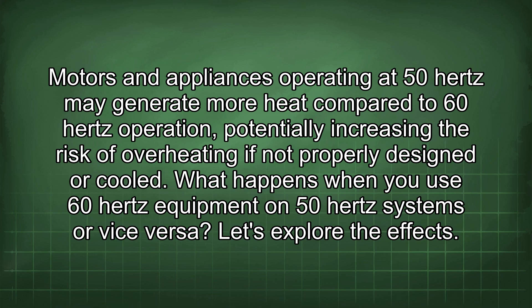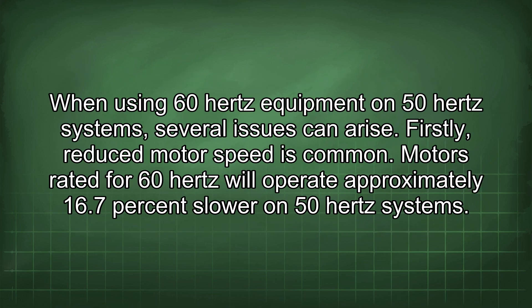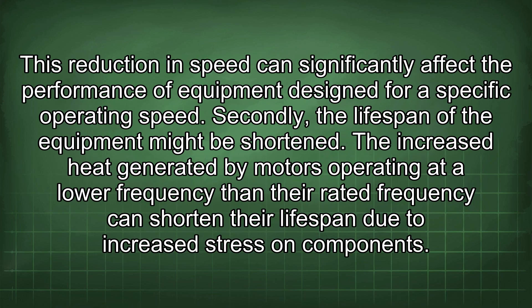What happens when you use 60Hz equipment on 50Hz systems or vice versa? When using 60Hz equipment on 50Hz systems, several issues can arise. Firstly, reduced motor speed is common — motors rated for 60Hz will operate approximately 16.7% slower on 50Hz systems, which can significantly affect performance. Secondly, the lifespan of the equipment might be shortened, as the increased heat generated by motors operating at a lower frequency can cause increased stress on components.